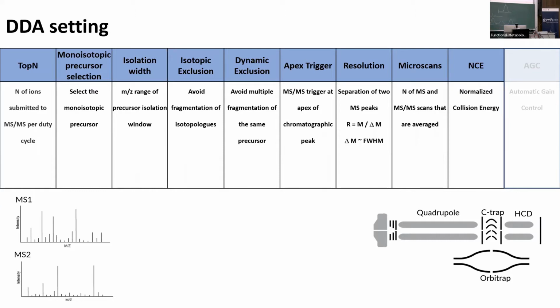There is an important thing. We can use stepped collision energy, which activates ions at different energies, which I particularly like because you never know what the ideal collision energy is. If you do that step thing, you hit it a little bit with everything and typically get a little bit richer spectra. Again, that depends on the instrument you have. Some can do stepped collision energy, others can't. So you need to figure out what's best. Often libraries are also acquired by default at different collision energies.